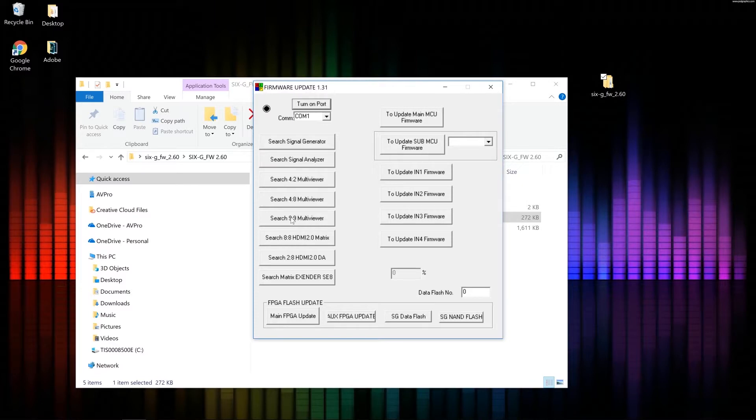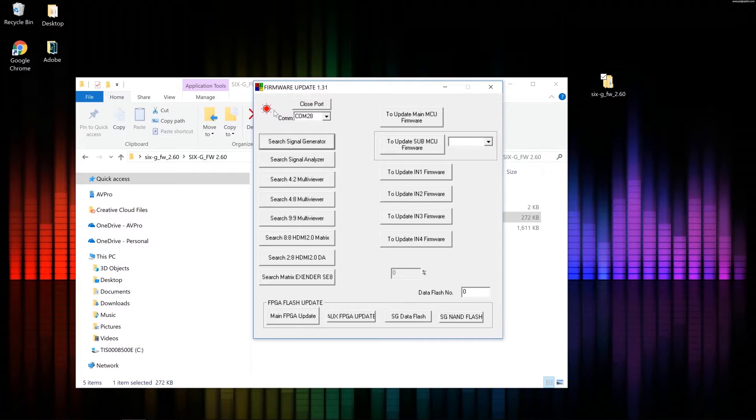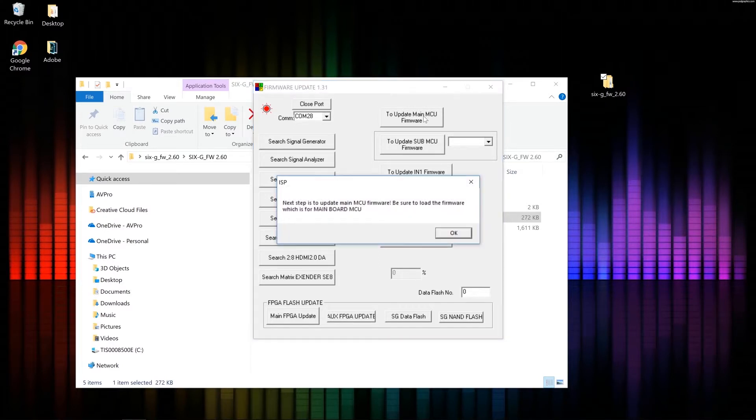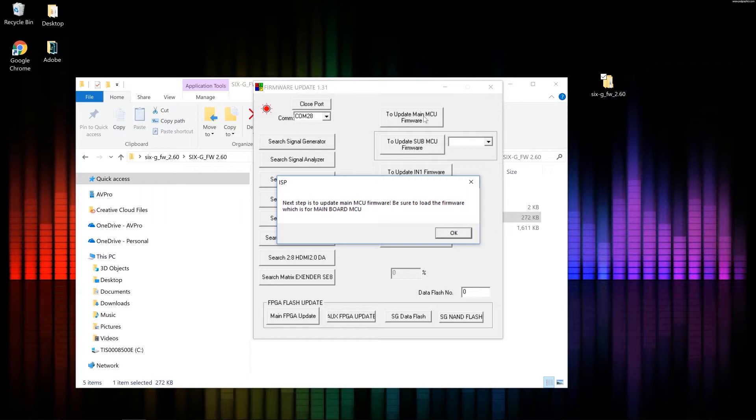First I'm going to click search signal generator. I've got a red light and a com port. That's a good sign. So last time I clicked main FPGA update for the first part of the firmware update. This time we're going to click the main MCU firmware update. That window just warned you, by the way, you're about to upload the MCU firmware. Okay.